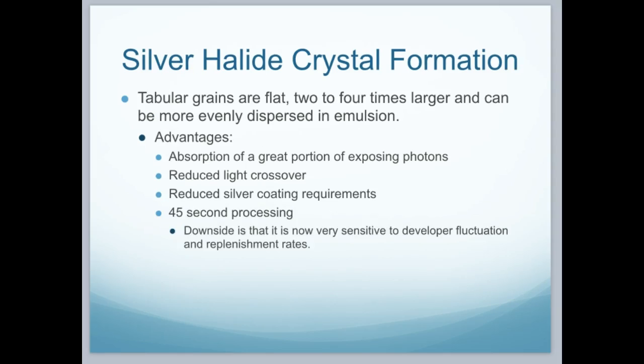These silver halide crystals are tabular grains that are flat — two to four times larger than other crystals that have been used, and can be more evenly dispersed in emulsion. The advantages include the absorption of a great portion of the exposing photons, reduced light crossover, reduced silver coating requirements — saving money — and 45-second processing, which is fast. The downside is that they are very sensitive to the chemicals in the processor, and we will see the importance of that chemistry as we talk about the processor.